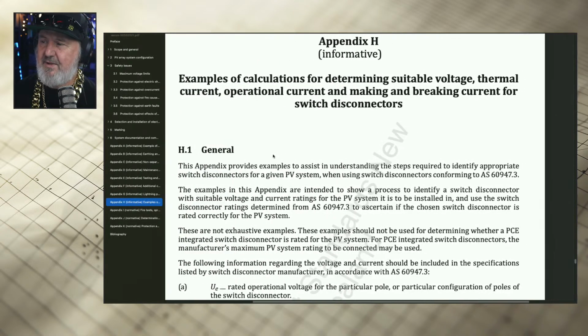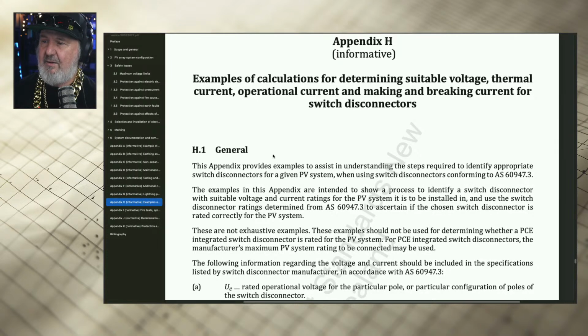So let's have a look at a worked example here. And this is an example of calculations for determining suitable voltage and thermal current. Now, what on earth is thermal current? What it means is that the rating of switchgear is actually derated with temperature. So as it gets warmer, the ability to interrupt fault or any currents diminishes.